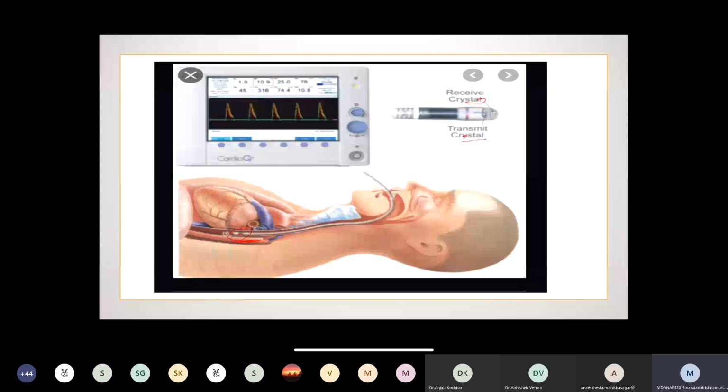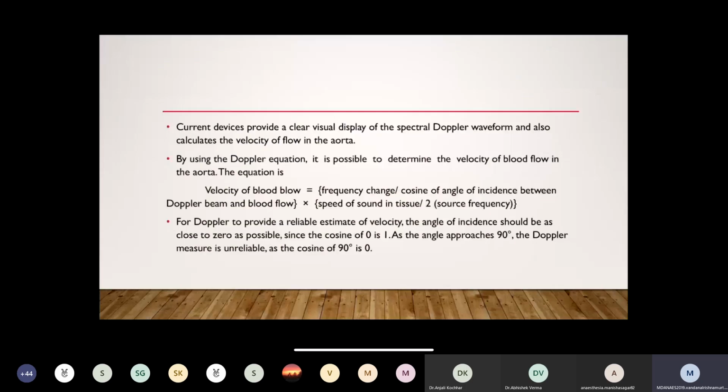As the velocity of cells in the aorta travels at different speeds over a cardiac cycle, the machine obtains a measure of all of the velocities of the cells moving over time. Mathematically integrating the velocity represents the distance that blood travels. Next, using nomograms, the monitor approximates the area of the descending aorta. The monitor thus calculates both the distance the blood travels as well as the area. The area and the length give the volume. Consequently, the stroke volume of the blood in the descending aorta is calculated.